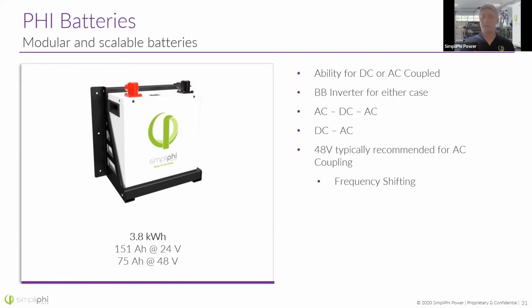range of equipment. So if you're retrofitting that old system with the FX inverters you mentioned, JP, this is the battery you're going to want to go with. There's no communications needed. That old equipment is going to be compatible. You'll just reprogram it through the Mate 3. So making sure to change the settings as you add these new batteries to the system is always important, but not having to upgrade to brand new equipment for a savvy customer that's got old equipment, that's a great advantage of this product.